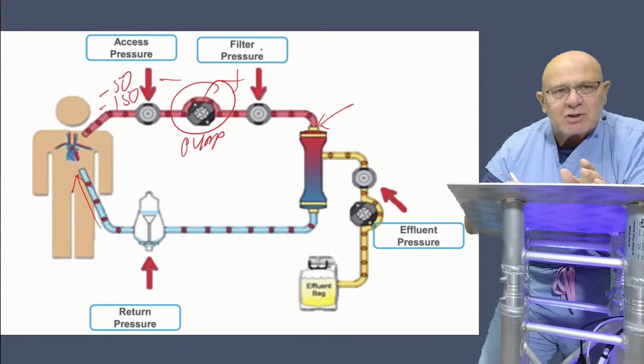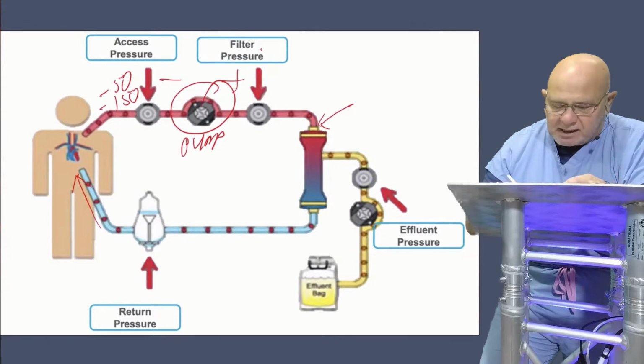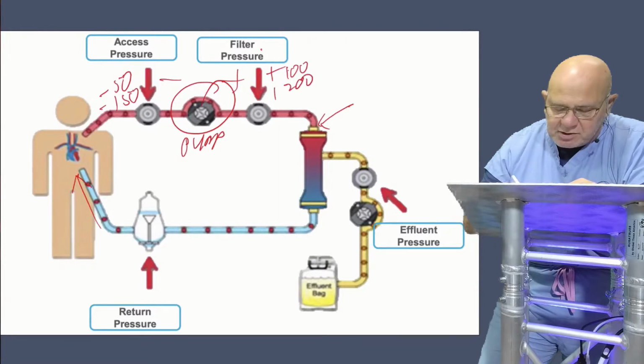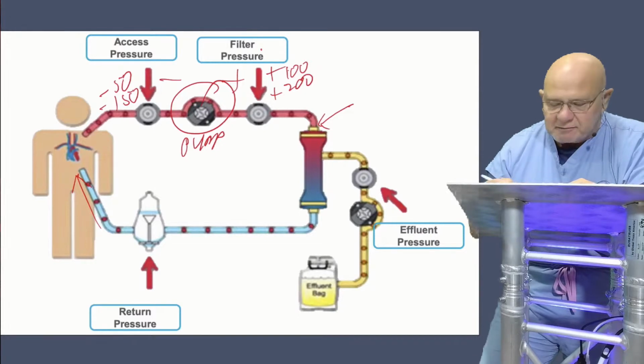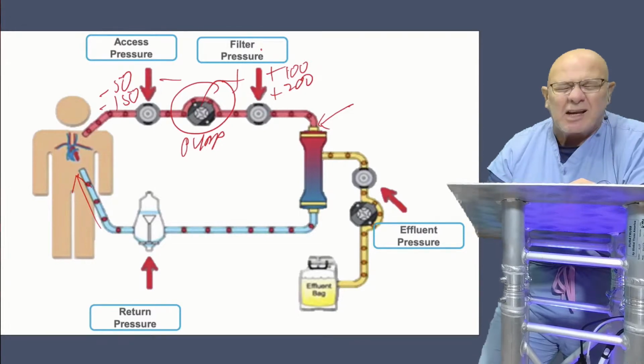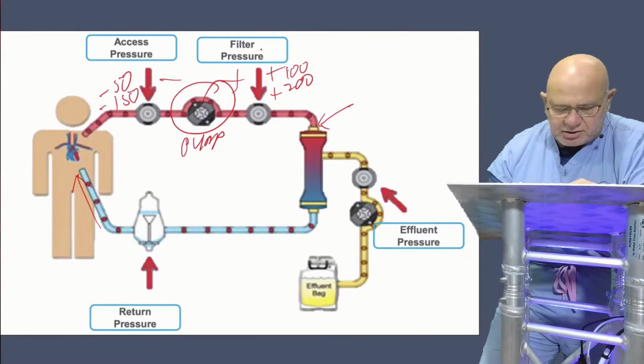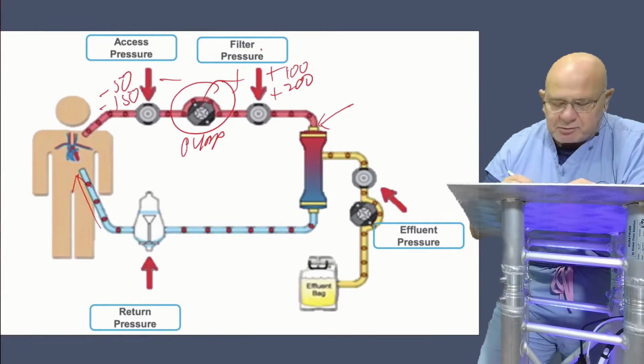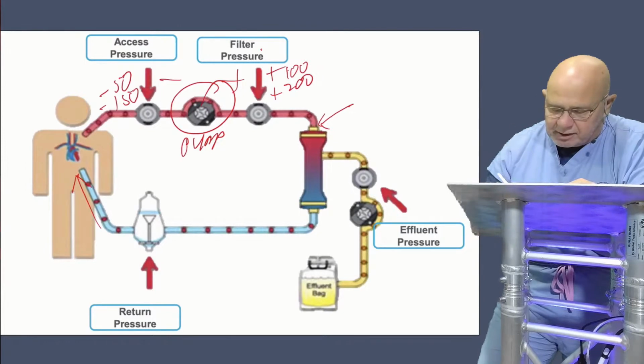And your filter pressure, depending on flows and all of that kind of thing, is going to be somewhere about, of course it's a positive number, right? So we'll say about 100 to 200, somewhere in that range. So it can range depending again on your flow and whether or not your return catheter is in a good spot. Usually these are double lumen. It shows it's separated, but usually it's a single catheter, right?